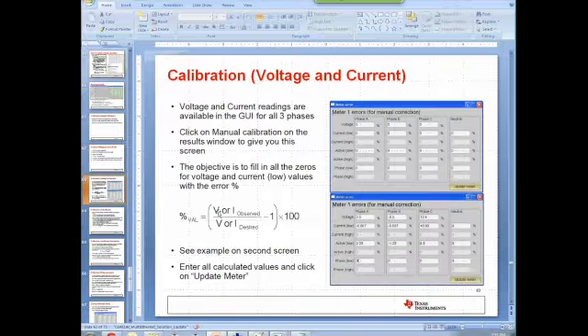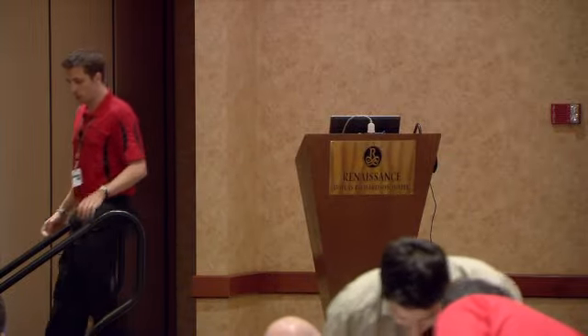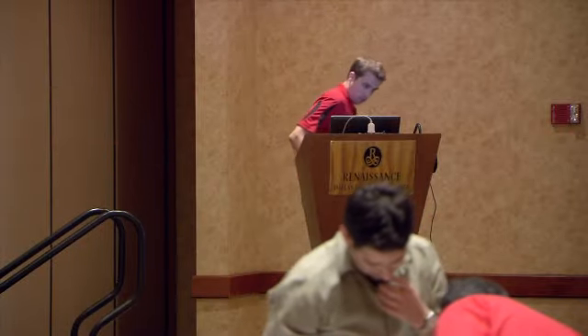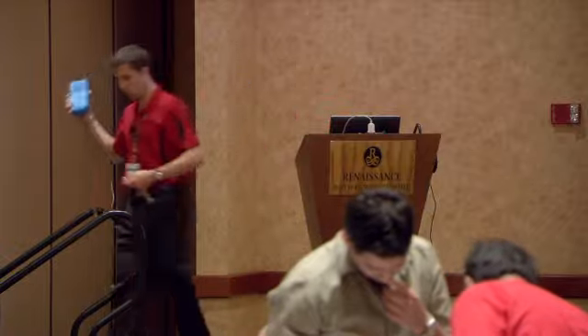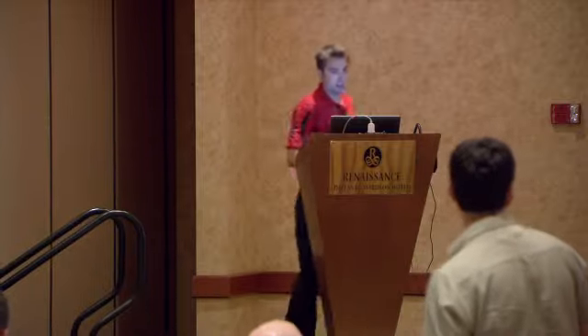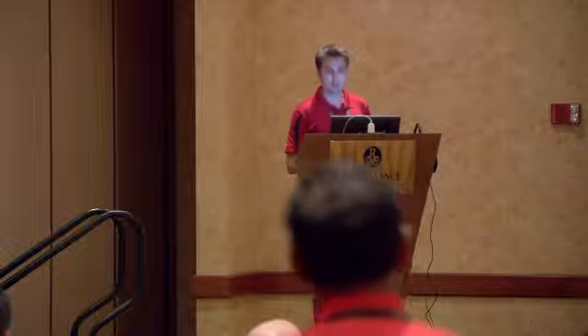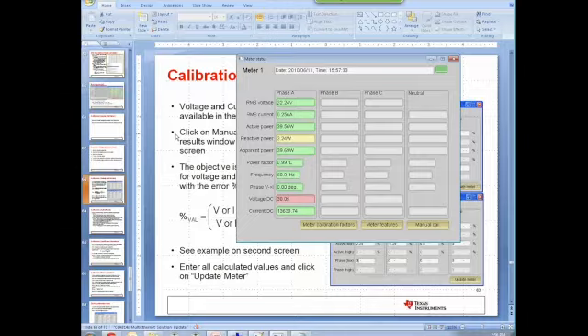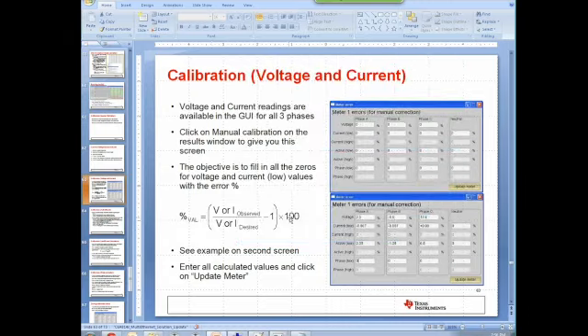So the next step is that we have to figure out what to enter into our GUI to tell it to change to the correct voltage. Once everyone has that, I guess we'll run around and make sure we're good on the meters, make sure none of those are too far off. Looks like everyone got to at least the reference voltage point. So we need to figure out from here what our meter needs to read moving forward. I'll go back to my slides here, I actually have it worked out. We have a simple equation for the value we enter into the calibration utility: our voltage observed over our voltage desired, that is, what we measured, minus 1, times 100.